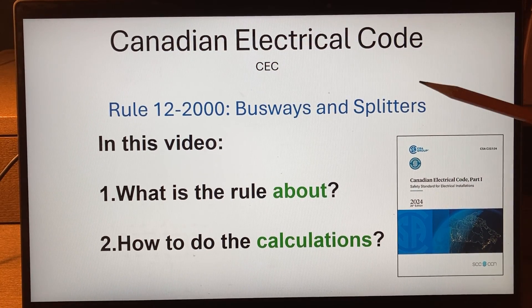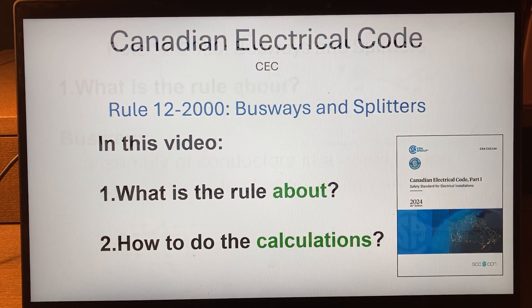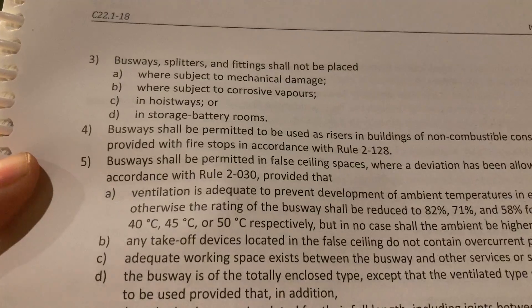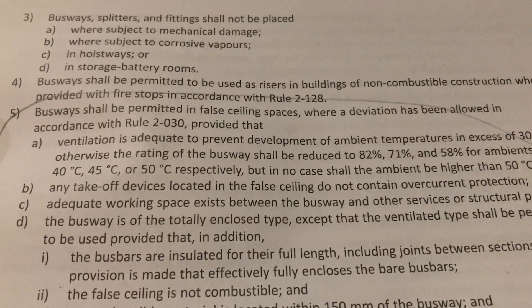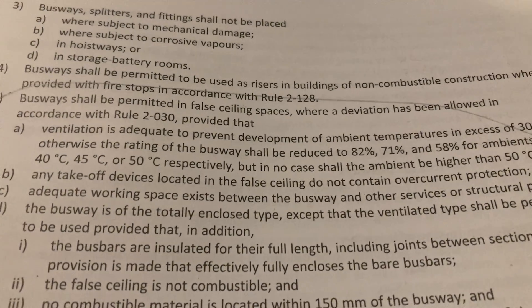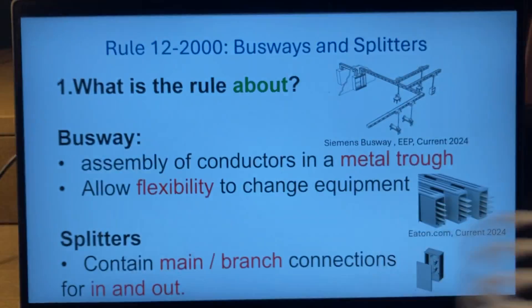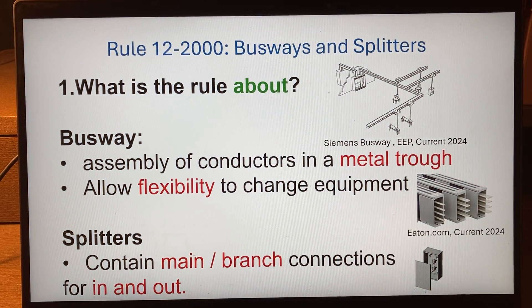I'm going to focus on rule 12-2000, and that's about busways and splitters. We're going to talk about what this rule is about and what the calculations are. You find this rule in the Canadian Electrical Code — busways and splitters — it has seven sub-rules. The calculations in this section are in sub-rule 5, which helps you calculate the ventilation that will be adequate to make sure you are not overheating inside these busways.